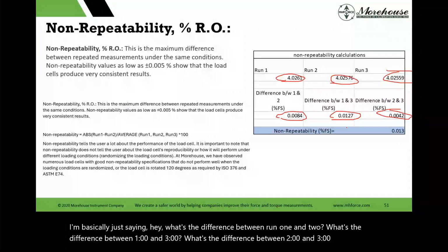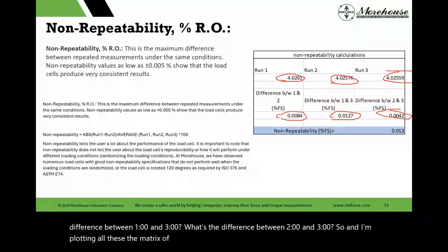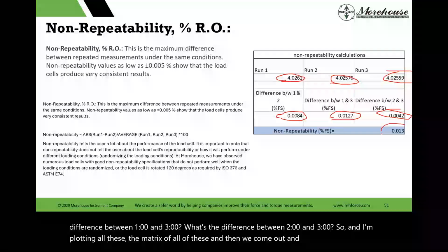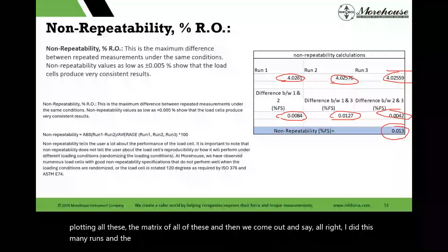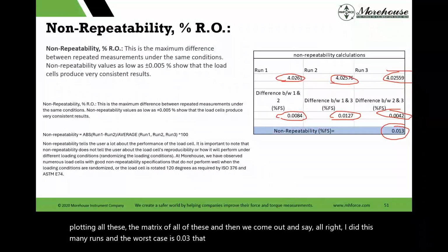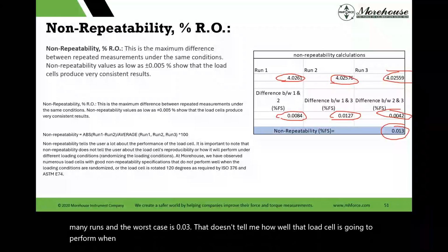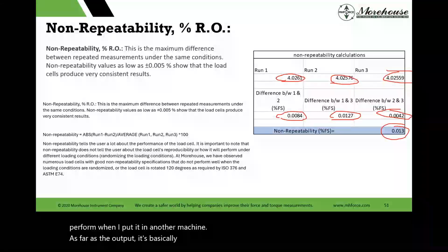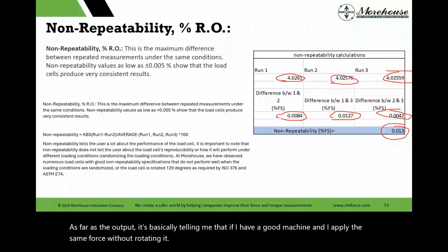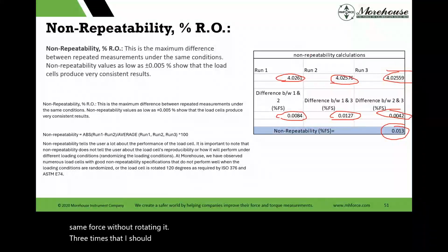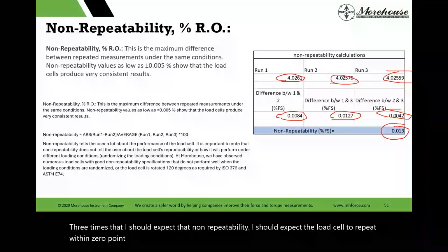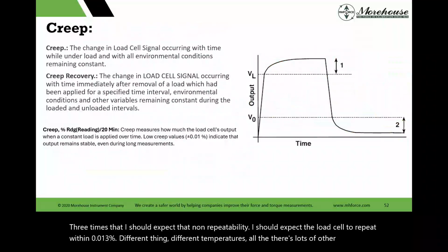And I'm plotting the matrix of all of these, and then we say, all right, I did this many runs, and the worst case is 0.03. That doesn't tell me how well that load cell is going to perform when I put it in another machine. It's basically telling me that if I have a good machine and I apply the same force, without rotating it, three times, I should expect that non-repeatability. I should expect the load cell to repeat within 0.013%. Different things, different temperatures, there's lots of other stuff that goes into this.